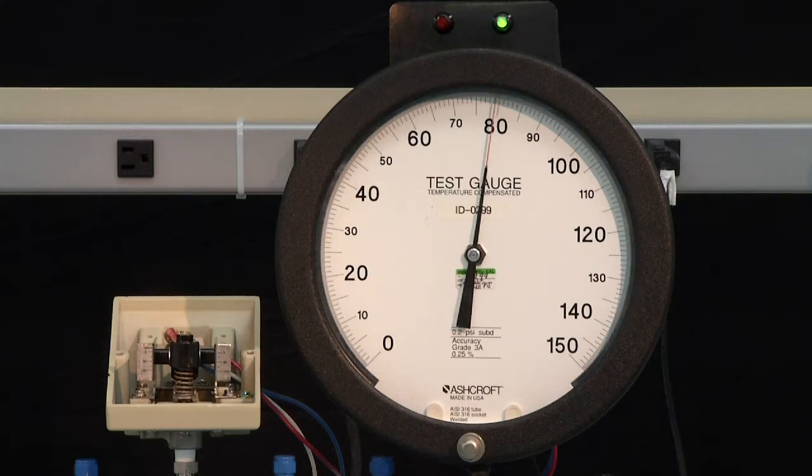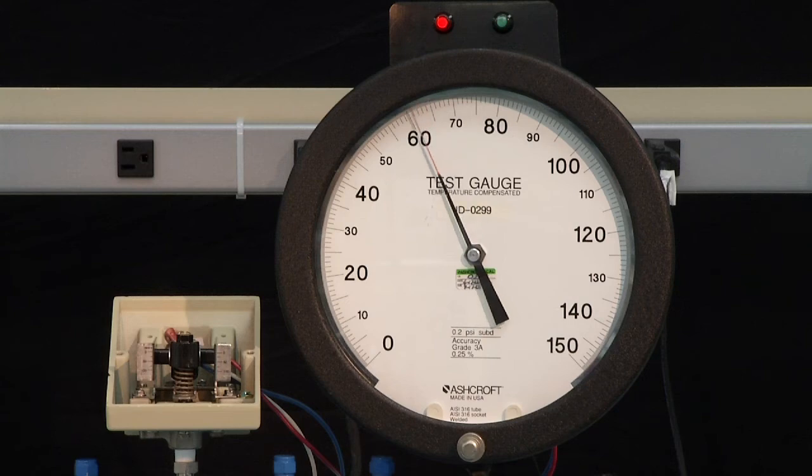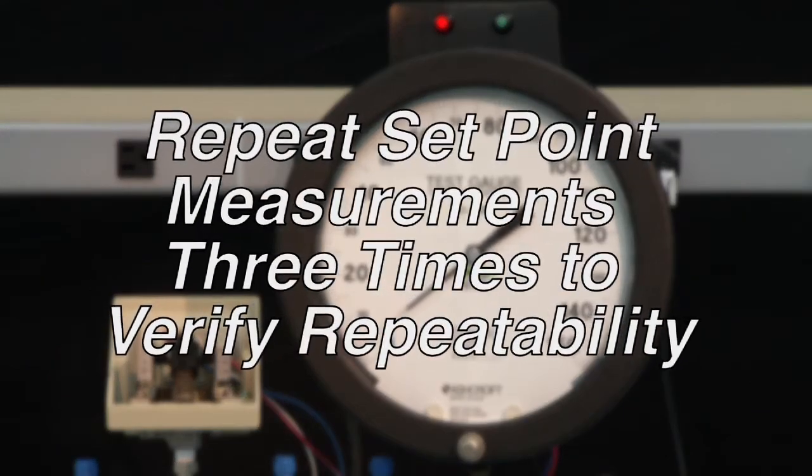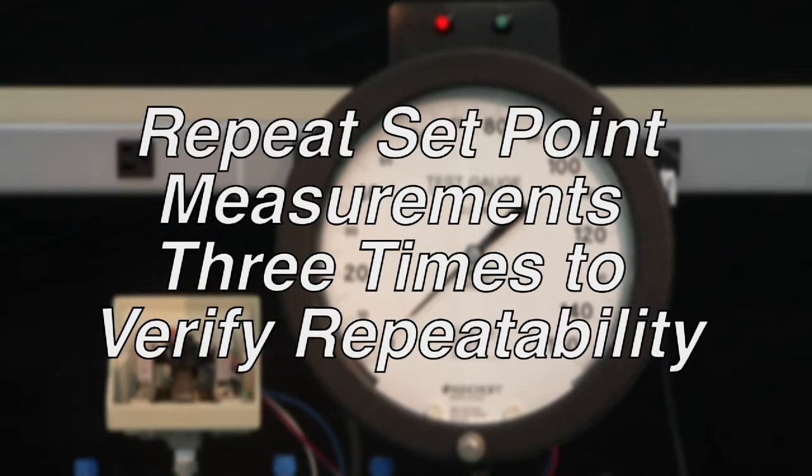And then we would go back very slowly and measure the deactivation for our dead band. That's our reset point. And then we would take it back to zero before we went up and measured the set point again. It is normal to repeat set point measurements three times to verify repeatability.